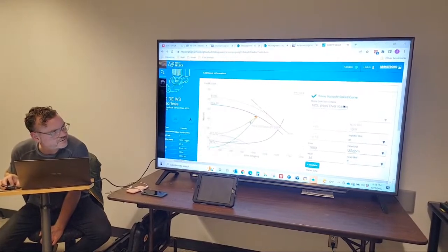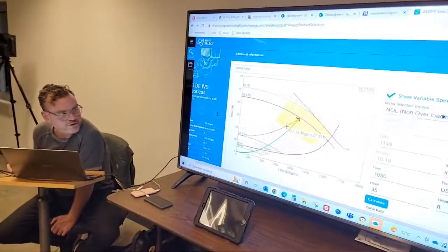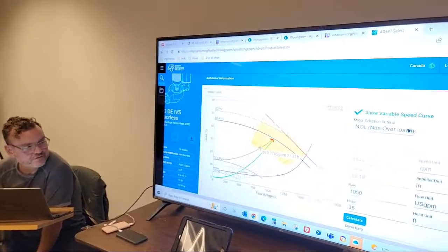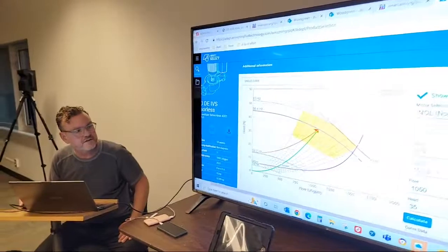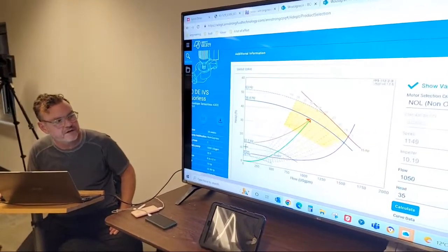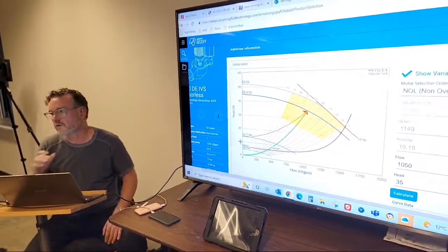So that's the system curve, so that represents the actual friction at the given flow. That's reality. This would be the control curve, right? So this control curve, they're giving me a control curve, 32 feet. This is a sensorless pump.